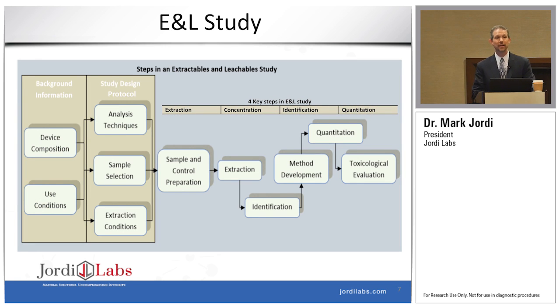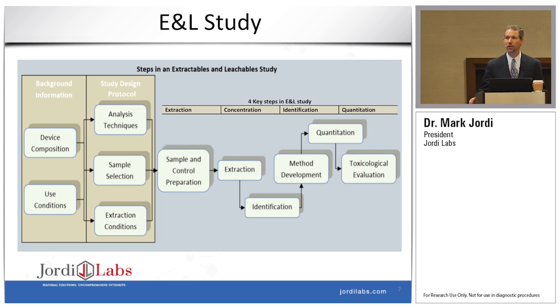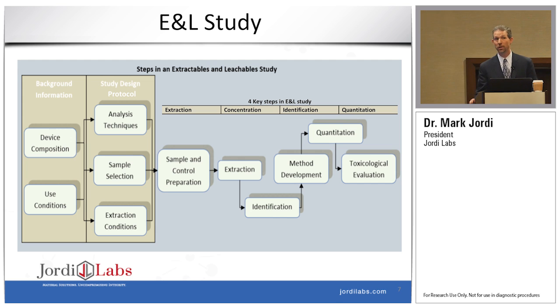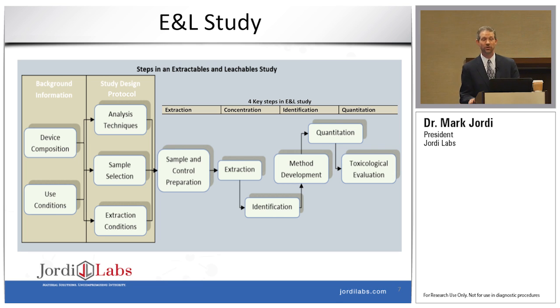In an E&L study, the main steps are shown in this figure. The first thing we want to do is carefully consider what are the materials of construction used in making the material that we're going to extract. The more data we have going into that study, the better we can predict what kinds of extractables and leachables might be present. We then spend time considering which analytical techniques we want to use, which is often controlled by which type of extractables we think are going to be present. Sample selection and extraction conditions are also very important.